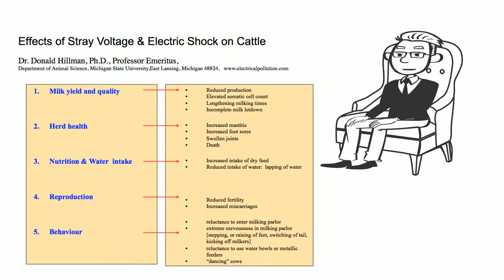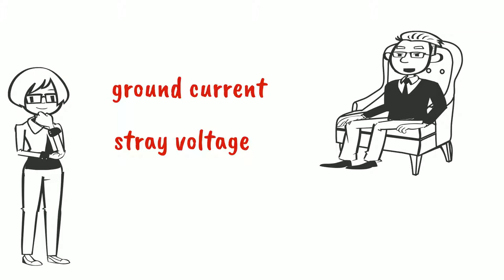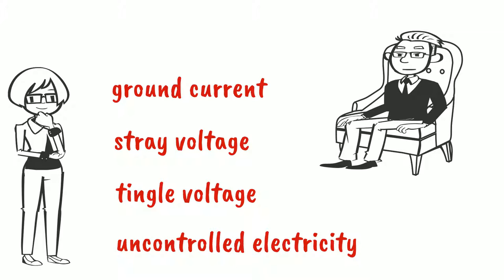A list of effects can be seen in this chart. We can go through them one at a time. Before we do that, I noticed that you refer to ground current as stray voltage. Can you explain that? Stray voltage was the term that was used for many years. It is easier to measure voltage than to measure current. Technically they are not the same, but some people use them interchangeably. Tingle voltage was also commonly used, and today some would like to refer to it as uncontrolled electricity.